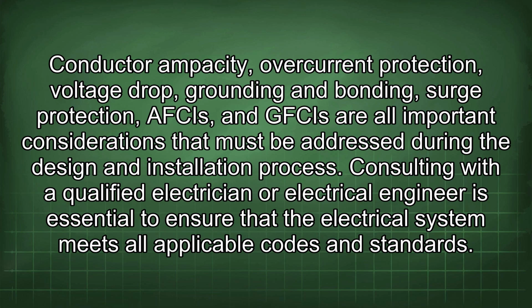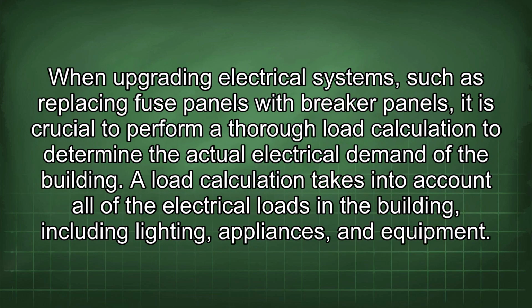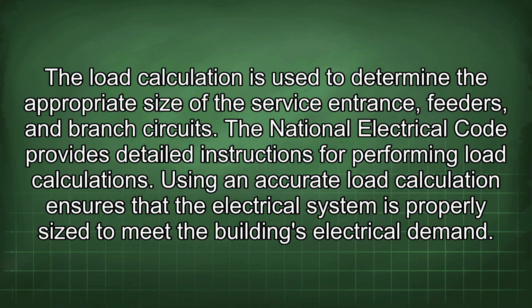When upgrading electrical systems, such as replacing fuse panels with breaker panels, it is crucial to perform a thorough load calculation to determine the actual electrical demand of the building. A load calculation takes into account all of the electrical loads in the building, including lighting, appliances, and equipment. The load calculation is used to determine the appropriate size of the service entrance, feeders, and branch circuits. The National Electrical Code provides detailed instructions for performing load calculations. Using an accurate load calculation ensures that the electrical system is properly sized to meet the building's electrical demand.